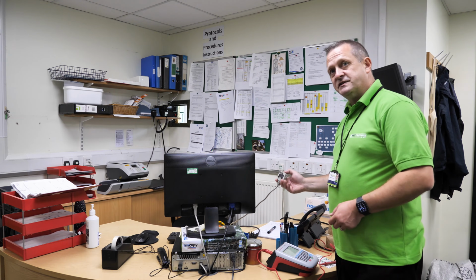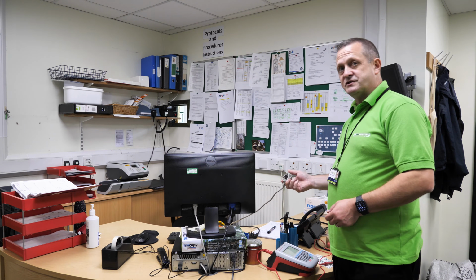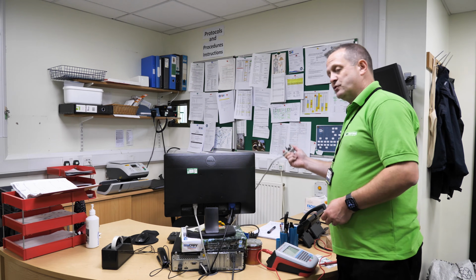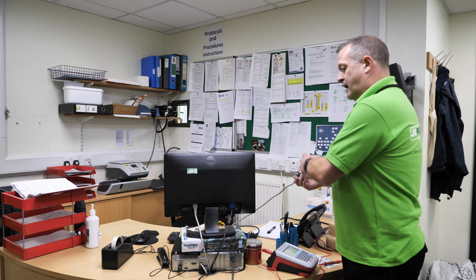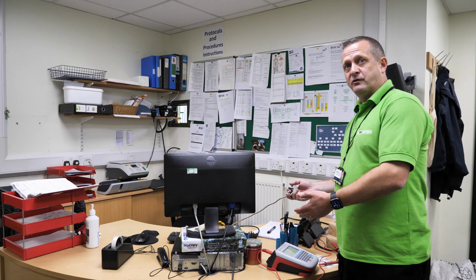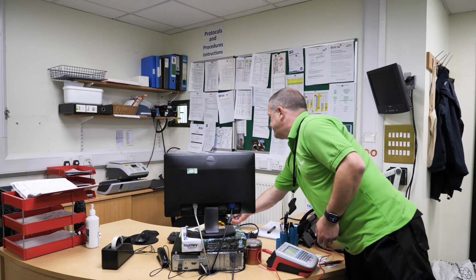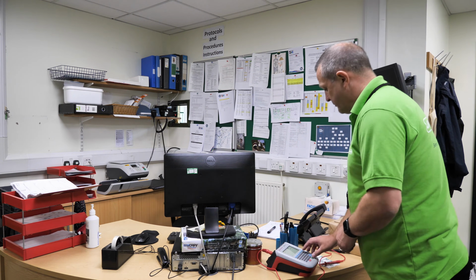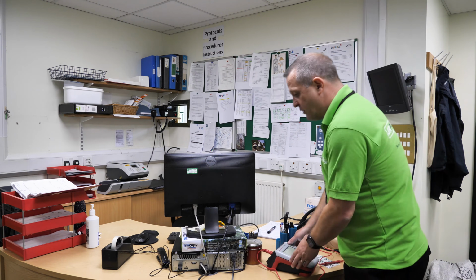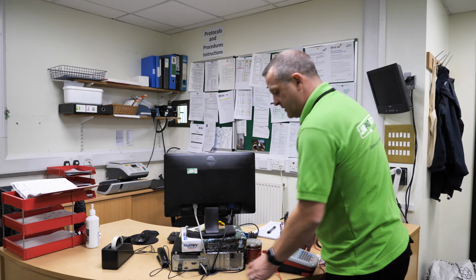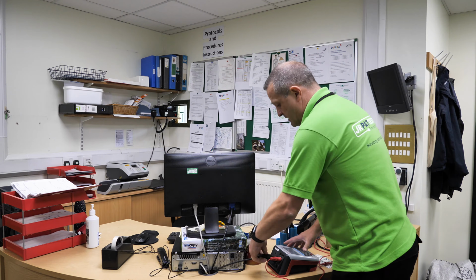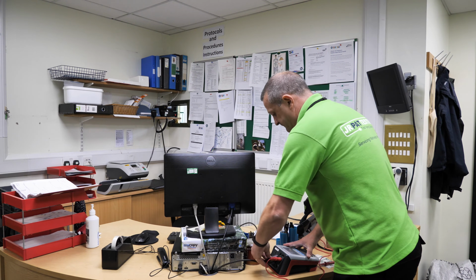What we need to remember, after conducting the test, is to conduct a functionality test just to make sure that the monitor is working. As we go to the computer base, I will check both of those at the conclusion of both tests. So onto the computer base.